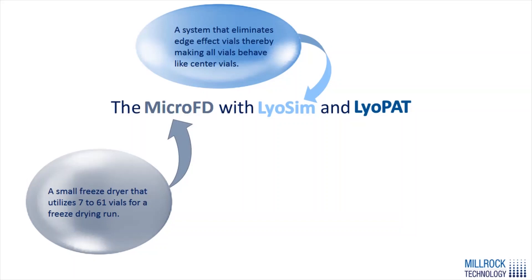This can't be done, for example, on a larger tray unit by just using a small array of vials, because that will not be representative of what a full tray will behave like. When we use the MicroFD with the LyoSim, it eliminates the edge effect so all the vials behave like center vials, and we can use this as a representative cycle for a larger freeze dryer.